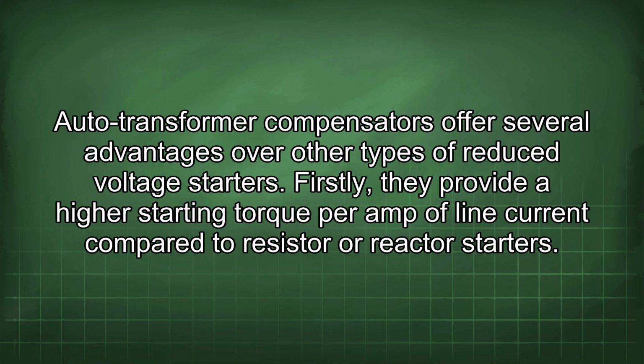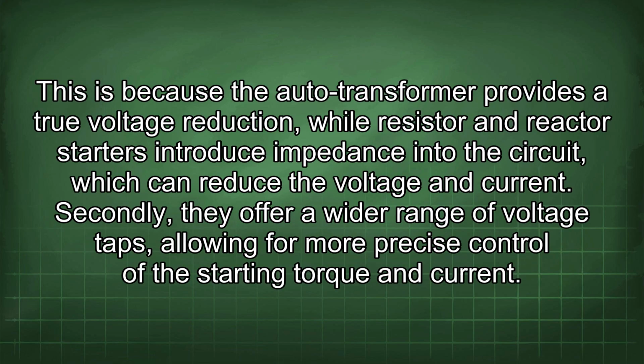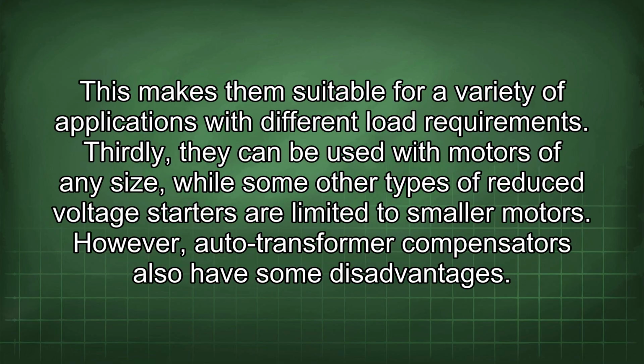Firstly, they provide a higher starting torque per amp of line current compared to resistor or reactor starters. This is because the autotransformer provides a true voltage reduction, while resistor and reactor starters introduce impedance into the circuit, which can reduce the voltage and current. Secondly, they offer a wider range of voltage taps, allowing for more precise control of the starting torque and current. This makes them suitable for a variety of applications with different load requirements.